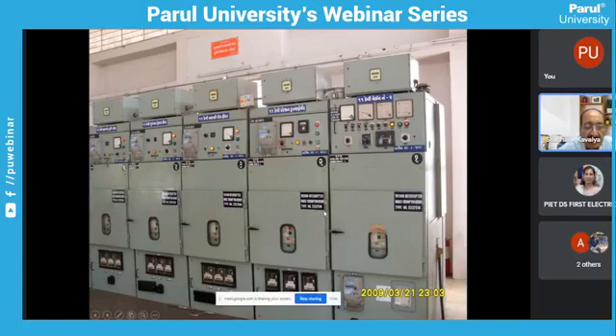So there is a procedure that first, when the breaker is out, you make the breaker on and off in test position or outside. Then you insert the breaker. Then there is a plug over here inside this thing. So you have to make the plug fitted in its junction, and then you have to again test it. Then you have to see that the breaker must be in off condition. This is an interlock. Breaker must be in off position.